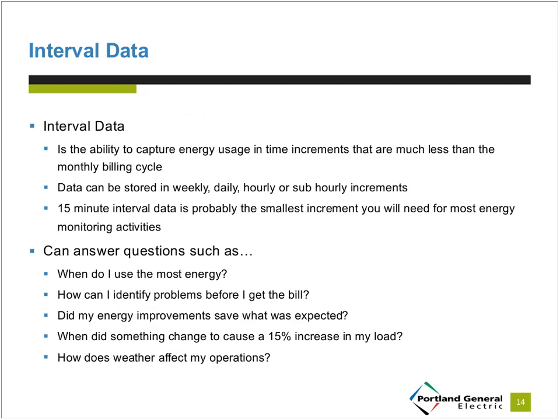But when they talk about interval data in the industry, it's really the ability to capture energy usage in time increments that are much less than the monthly billing cycle. Data can be stored weekly, daily, hourly, or even in increments that are less than an hour. 15-minute interval data is probably the smallest increment that you'll need for most energy monitoring activities, and most of the tools available today do look at 15-minute interval data.